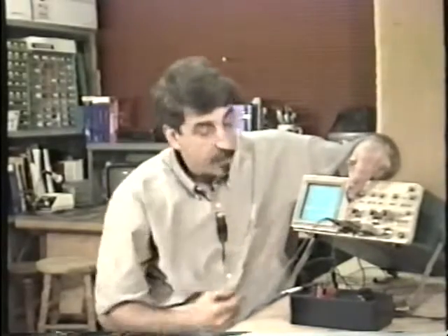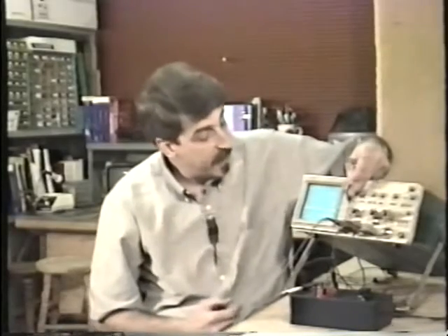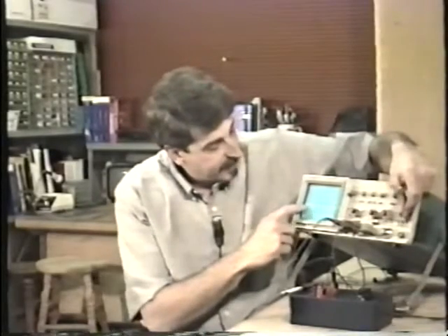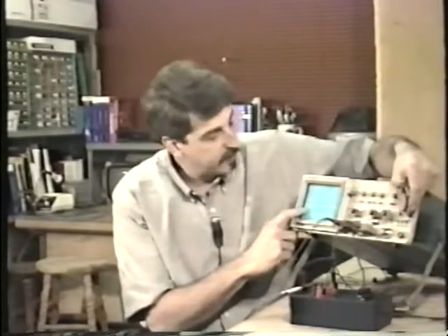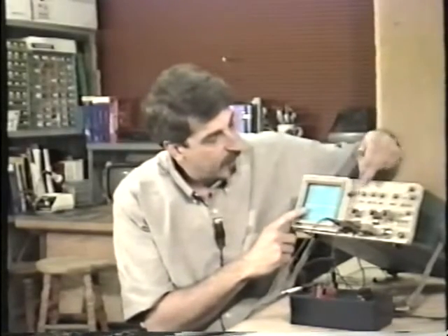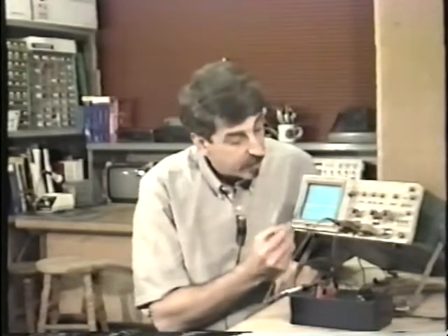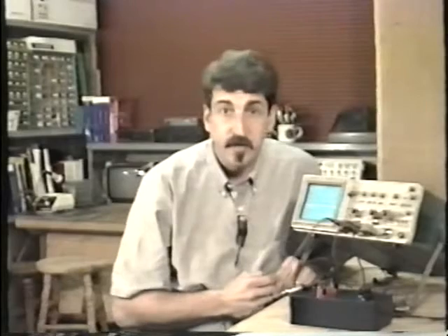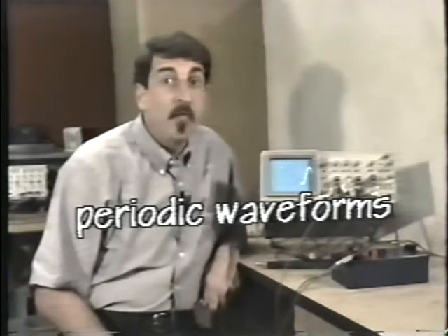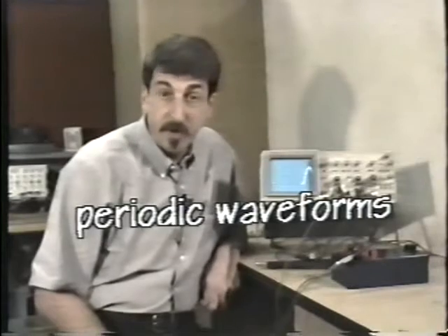In fact, the beam is going by so fast I actually have to turn up the intensity to even see what we're looking at. And what I see is a tiny little bit of what's known as ringing over here. It's really barely discernible, and nothing unexpected, certainly. But right now, this beam is moving really quickly from left to right. 0.05 microseconds per division. That's 50 billionths of a second for the beam to move each horizontal division on the graticule. Quite often the waveforms that you're looking at are what's known as periodic waveforms. That is to say, the waveform will repeat itself after a certain period of time.